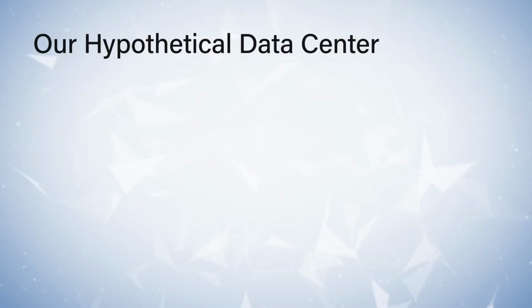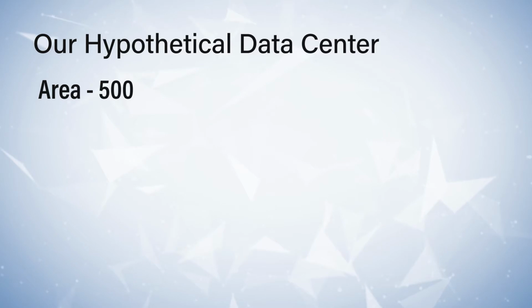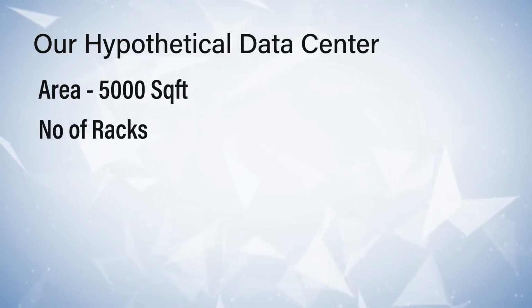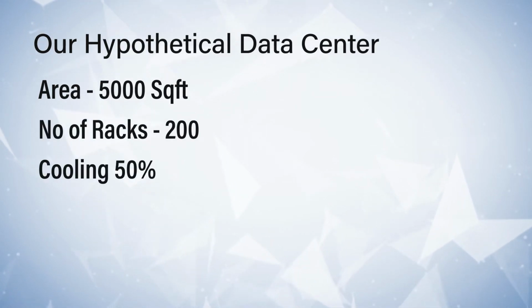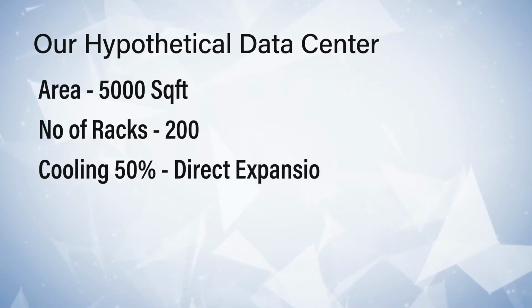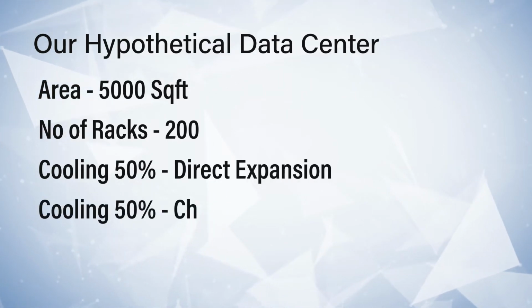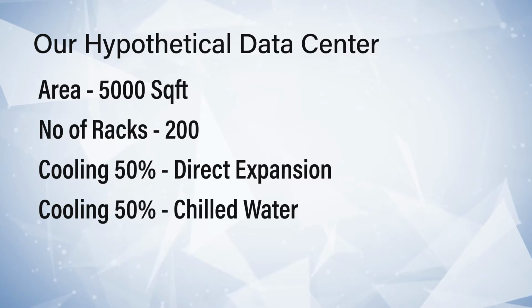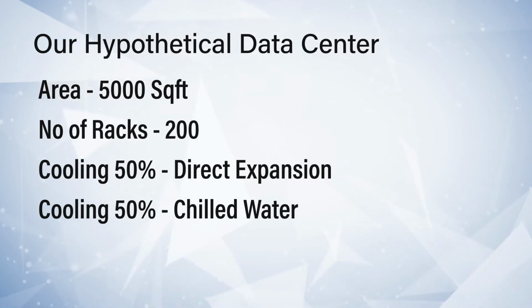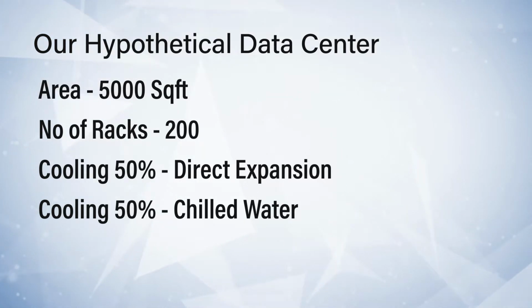Let us understand the calculation with an example of a hypothetical data center which is about 5000 square feet, and it will have 200 racks, half of which will use direct expansion or air cooling and half will use water based cooling. Cooling is a much bigger topic that we will cover in our upcoming videos. Now, based on this hypothetical data center, first let's determine the size of the critical load, the one that we mentioned earlier. So what is critical load?